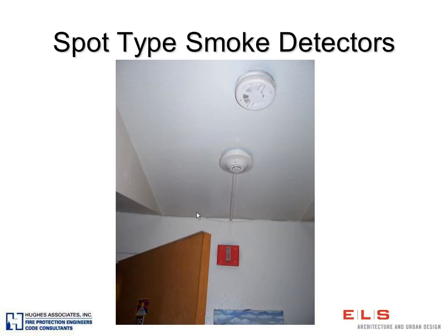For smoke detectors, we also have several different types. What you see in this photograph here are two different detectors. This was the original. This is a sleeping room. This is actually in a project that is in a historic district in Yosemite, and this is an employee housing sleeping room. And within this room, there were originally battery-operated smoke detectors installed within the rooms, and then at a later date, the facility came back in and installed wired smoke detectors, 120 volt. I'm sorry, I take that back.